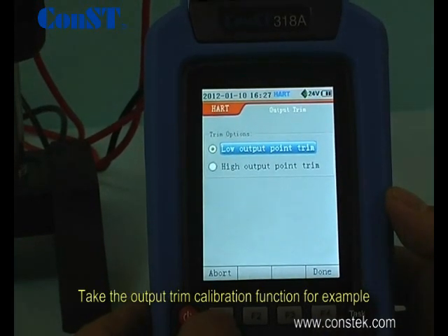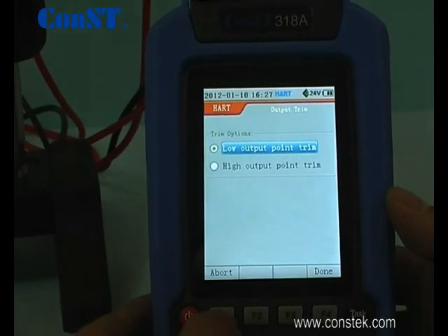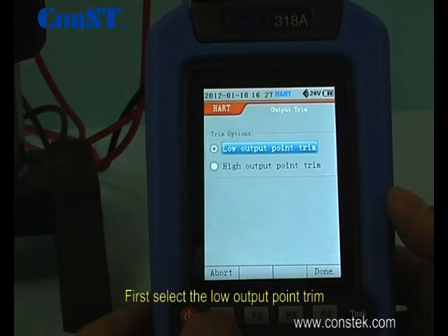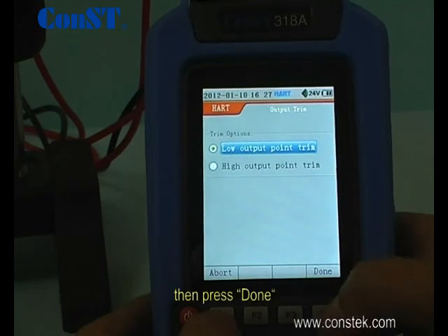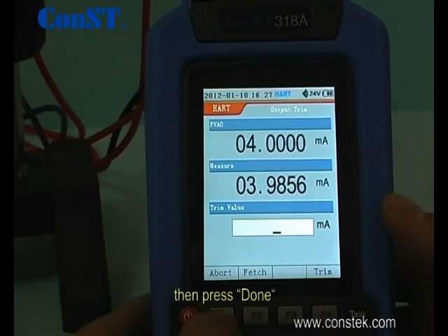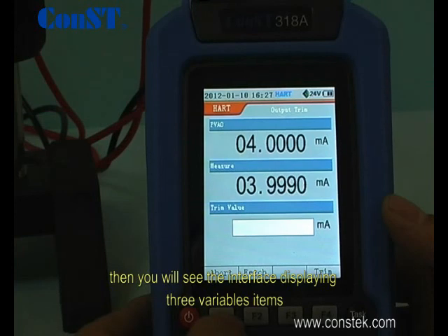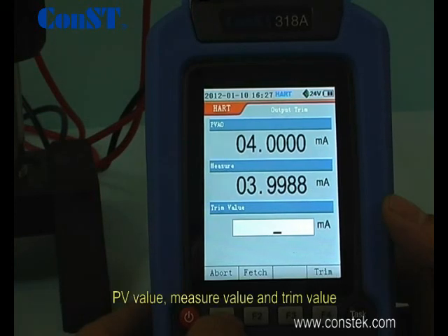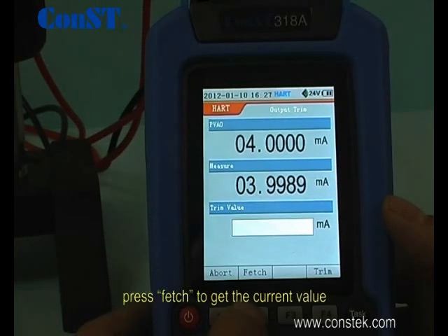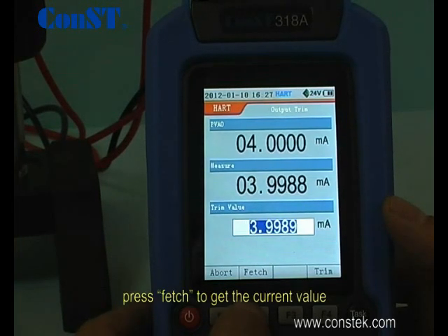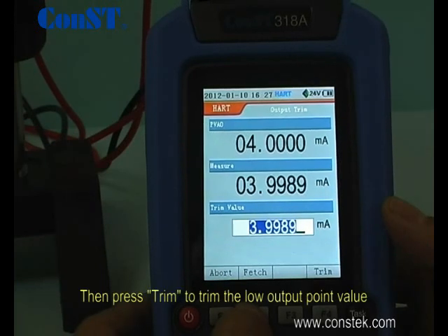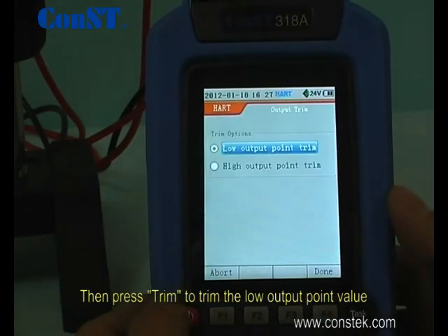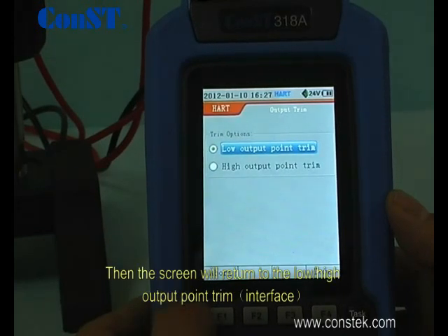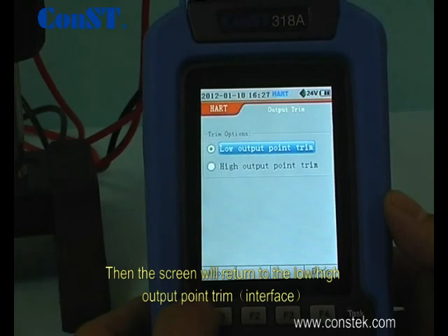Take the Output Trim Calibration function, for example. First, select the low output point trim, then press Done. Then you will see the interface displaying three variable items: PV value, measure value, and trim value. Press Fetch to get the current value. Then press Trim to trim the low output point value. Then the screen will return to the low-high output point trim.